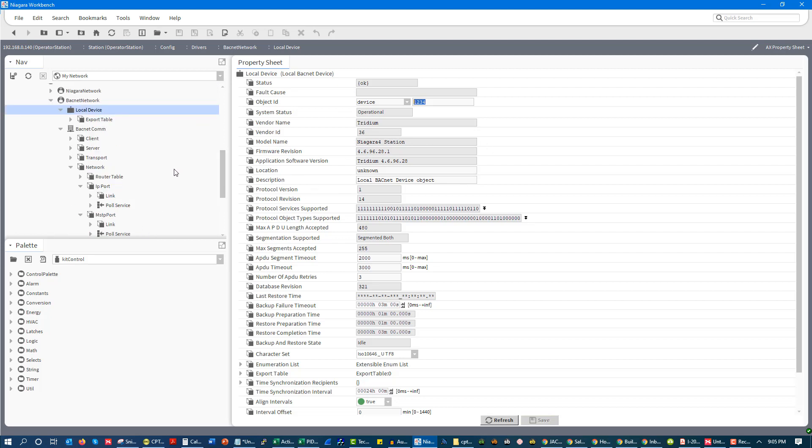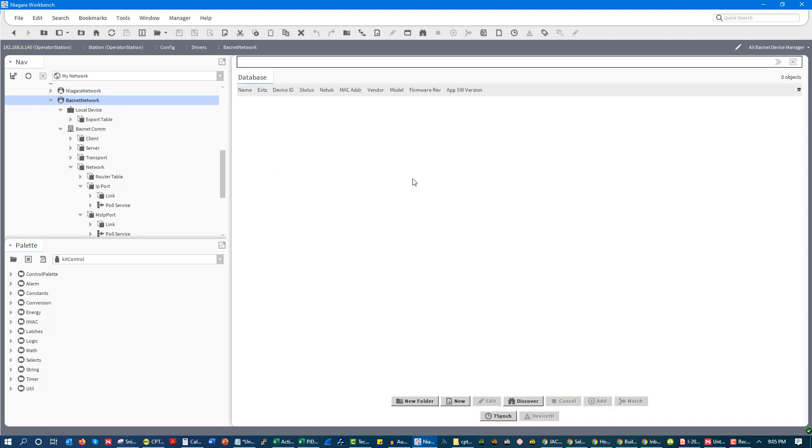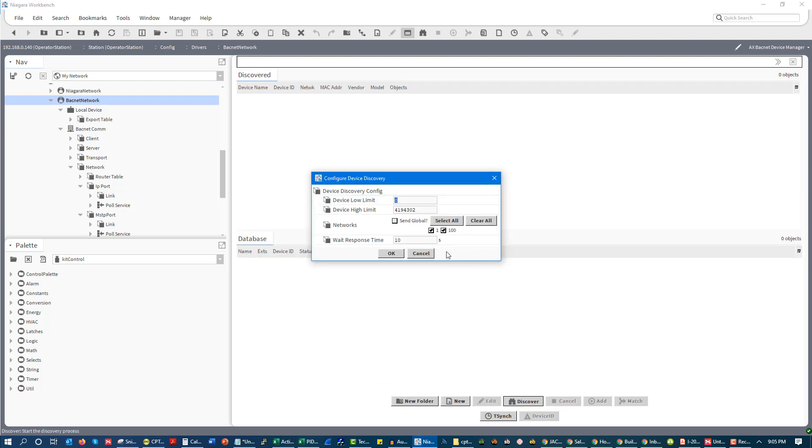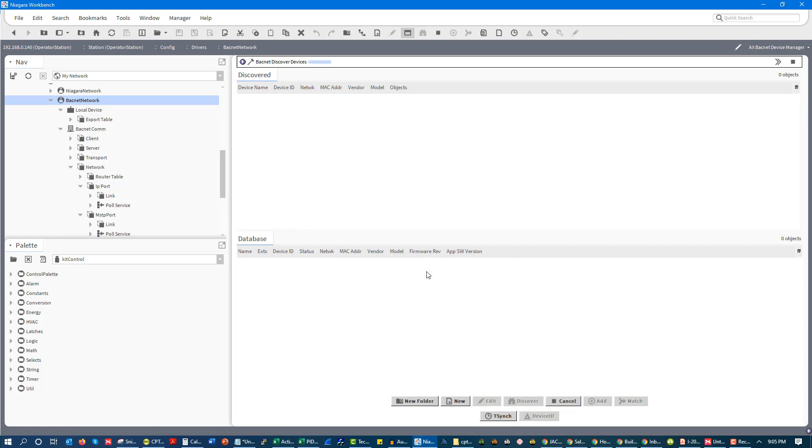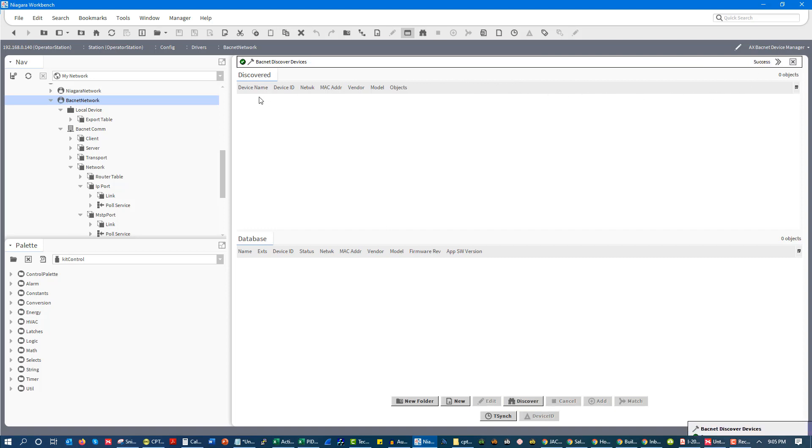So now to discover our devices. In order to go about discovering devices, and this will look different depending on which vendor software you're on, but you go to, in this case, BACnet network. We pick discover. We're going to look at our IP network because it's a lot faster. We're going to limit our range because I already know that our controllers are within the 1,000 to 1,100 range. So we're going to hit that, and we are going to do our discovery. And discovery will go for a little while.